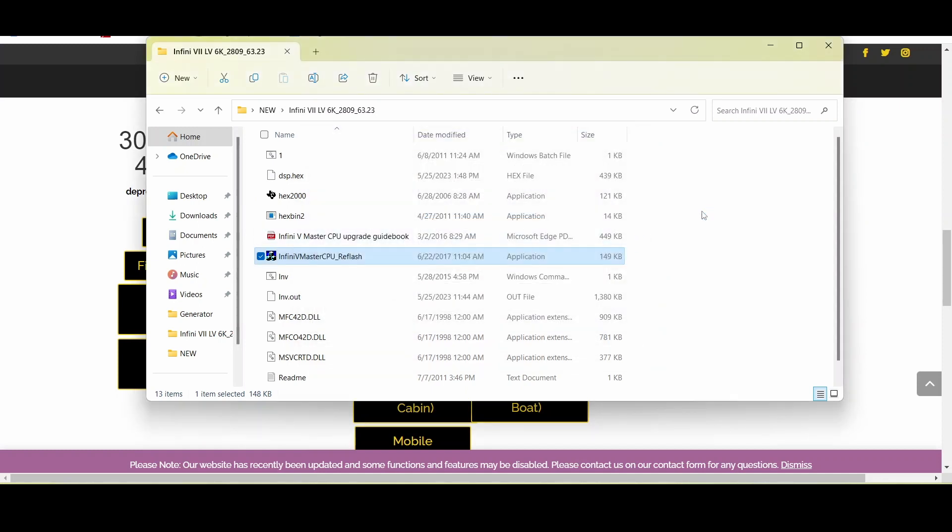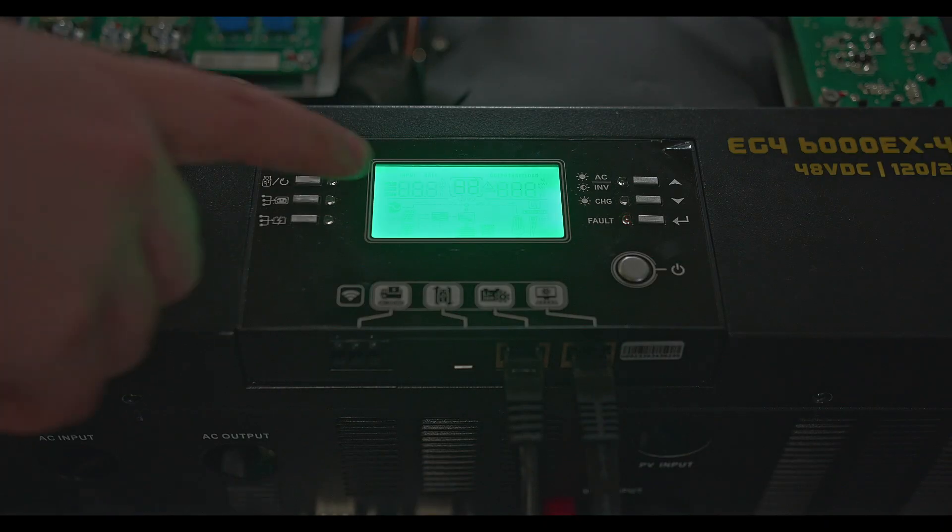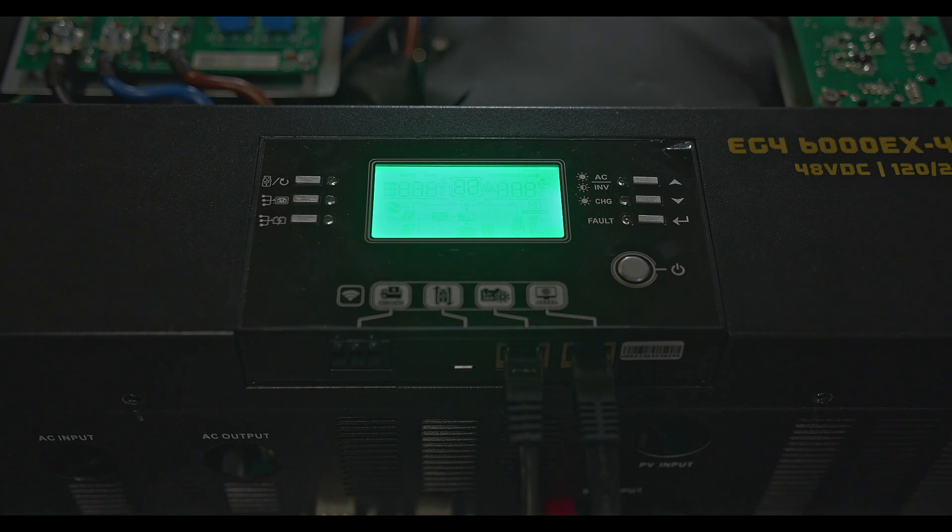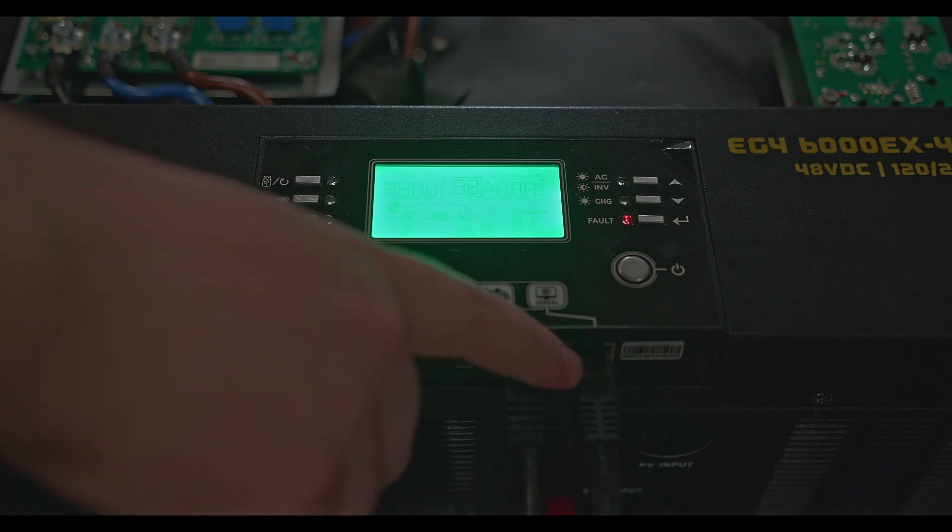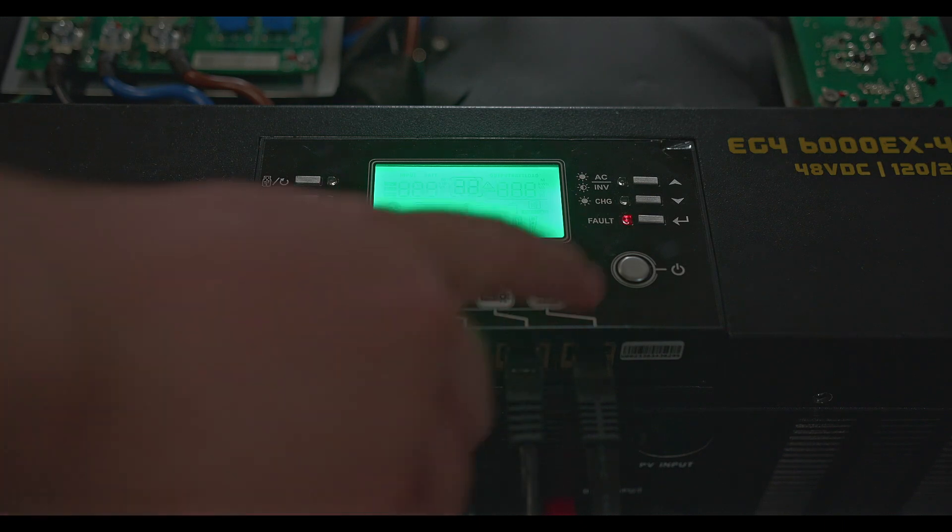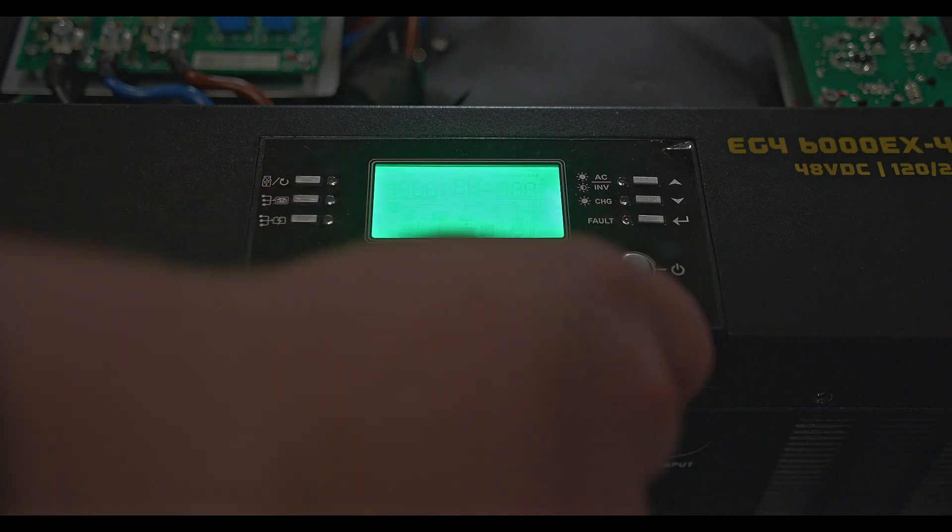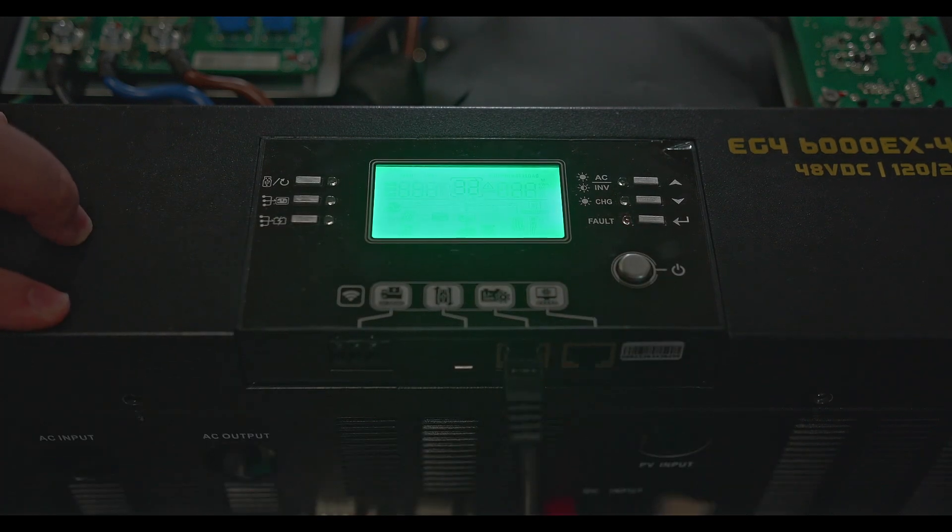Back at our inverter we may still see an error 32 now that we've updated both firmwares and that's usually because we still have this cable plugged in. So we want to go ahead and power cycle it again, but we want to make sure that we have the firmware update cable removed so we'll set that aside and we'll let it reboot.